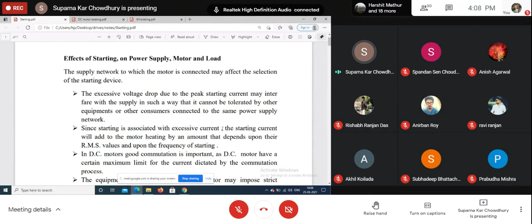So if the starting time is longer, maybe due to the high inertia or type of the load connected to the shaft, then it is important. The starting current will add to the motor heating by an amount that depends on their RMS values and upon the frequency of starting. So if it is an intermittent duty type load that is stopped and started frequently, then it affects the temperature rise. So in DC motor, commutation is important.